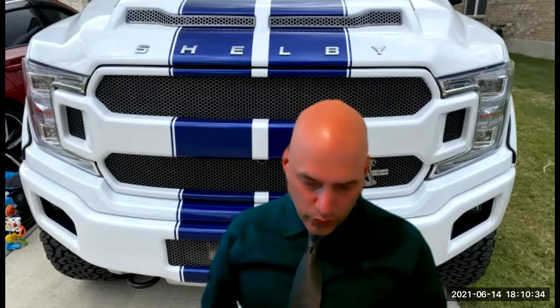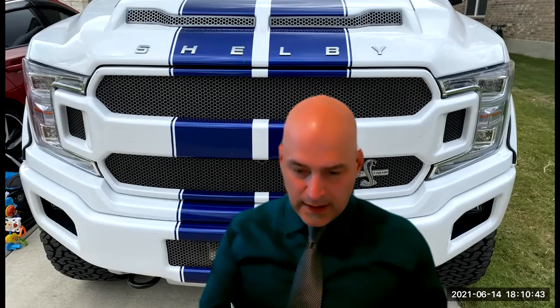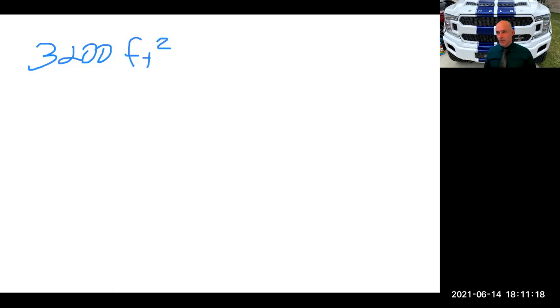So, a 3,200 square foot home, that's a really common square footage they've used for a long, long time. And that is the optional method unless they mention otherwise. And since they didn't, we're just going to presume that. I think I made a mistake on this one too. I think in my head I used 3,500 instead of 4,500 for the small appliances. So it's 1,500 times 3, so it'd be 4,500.